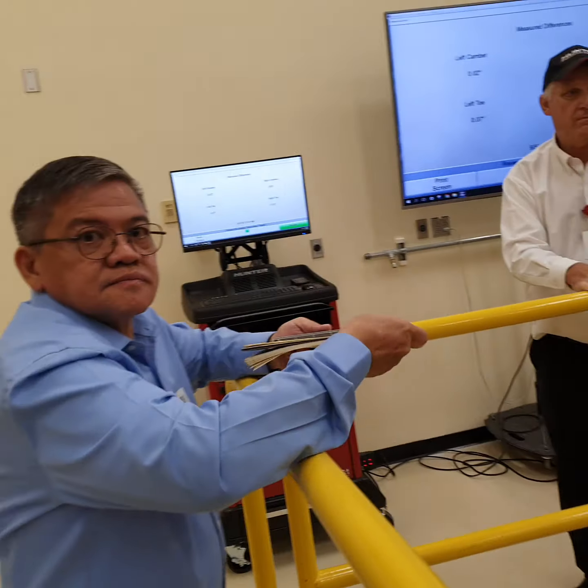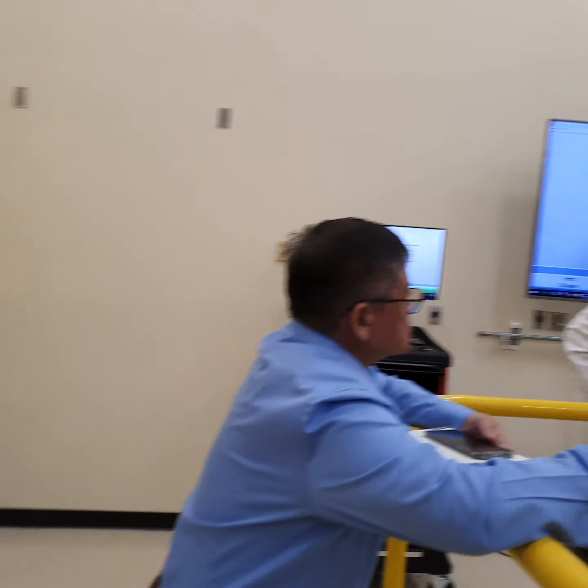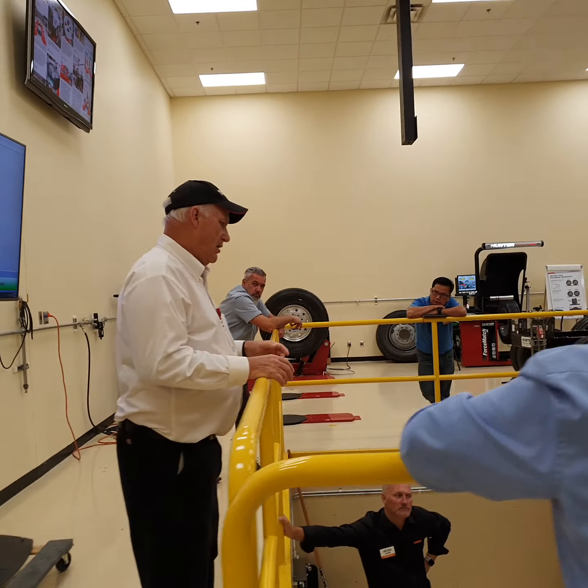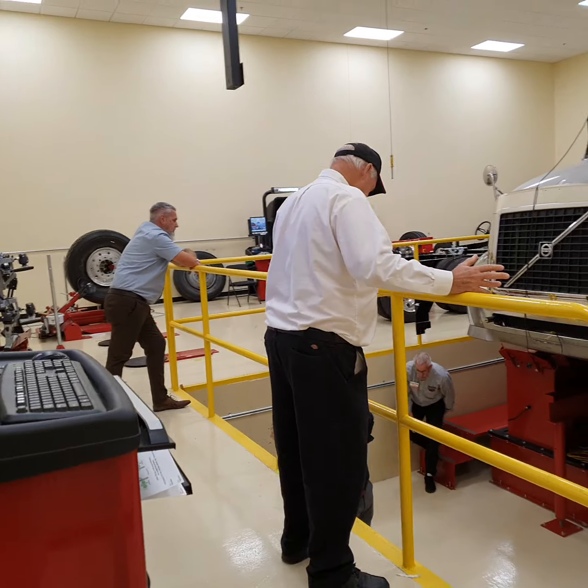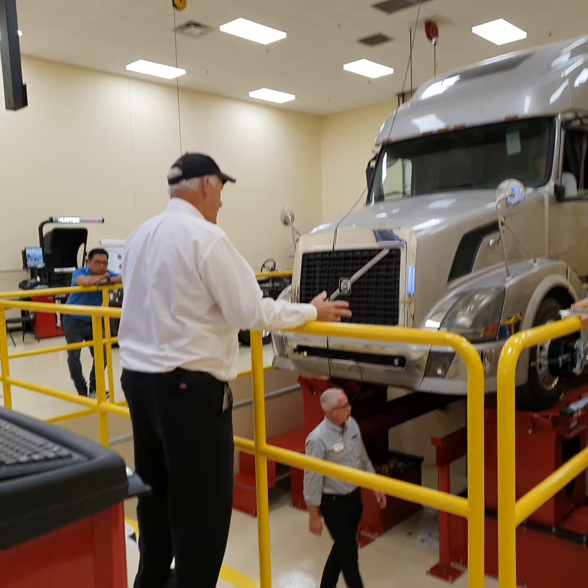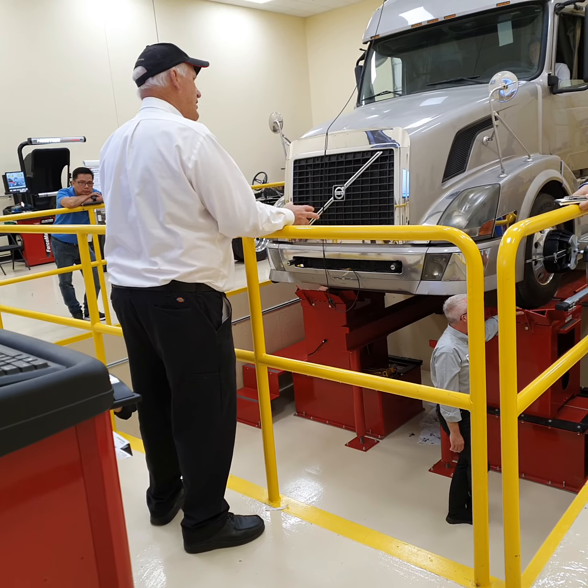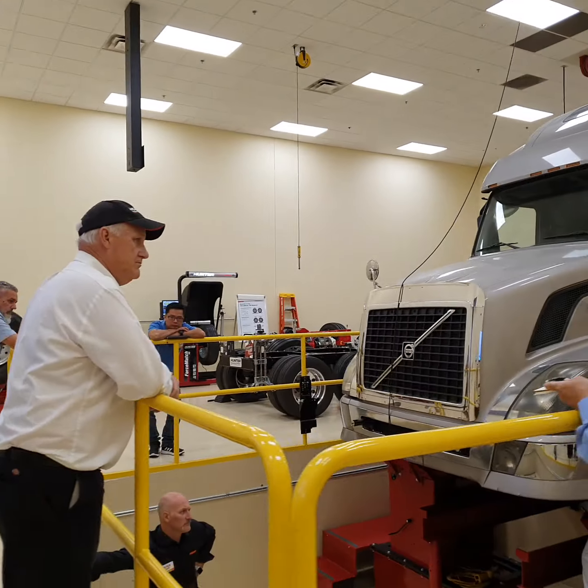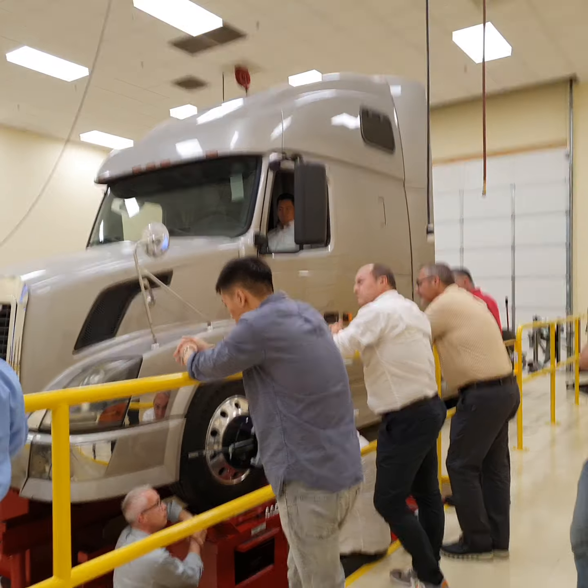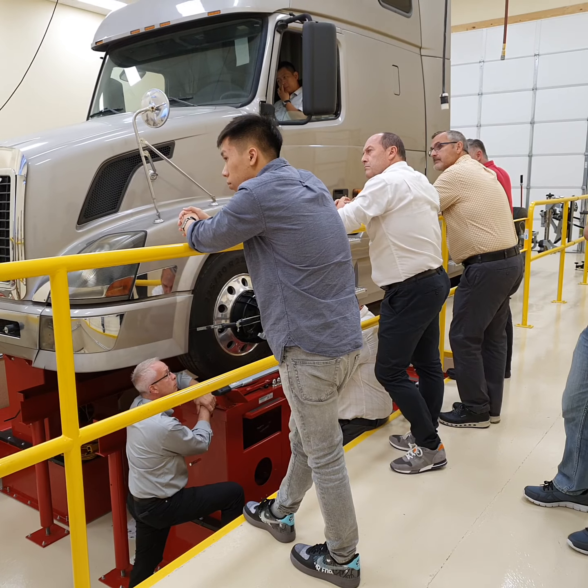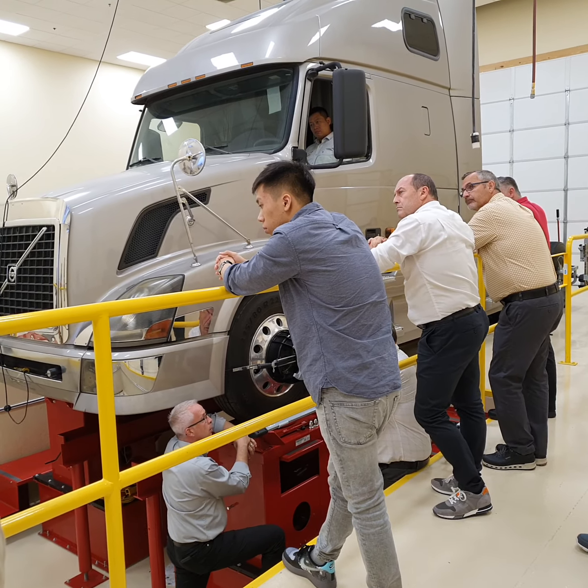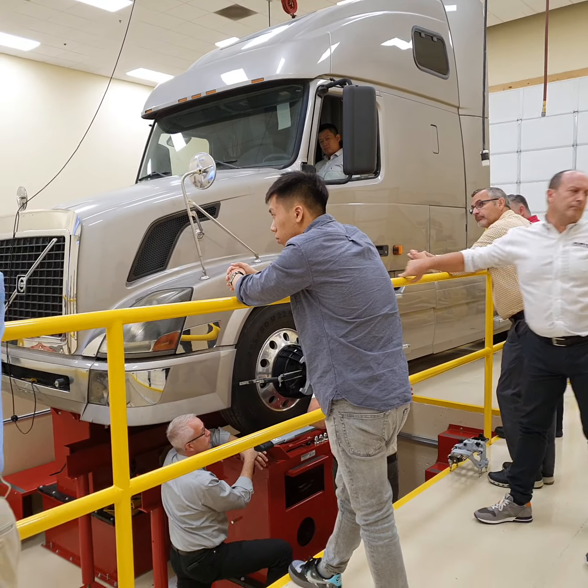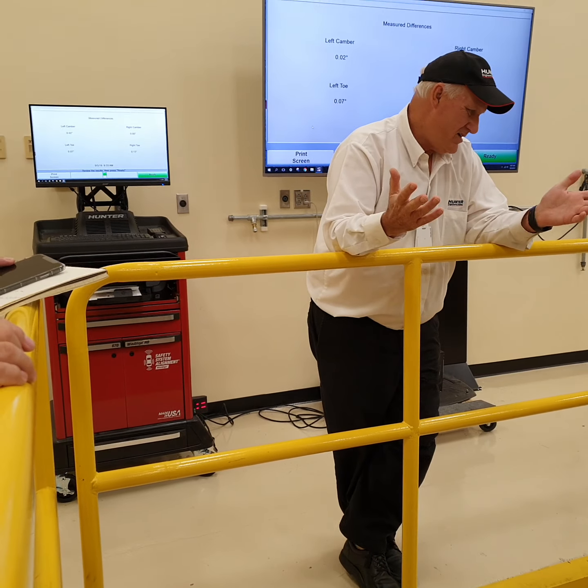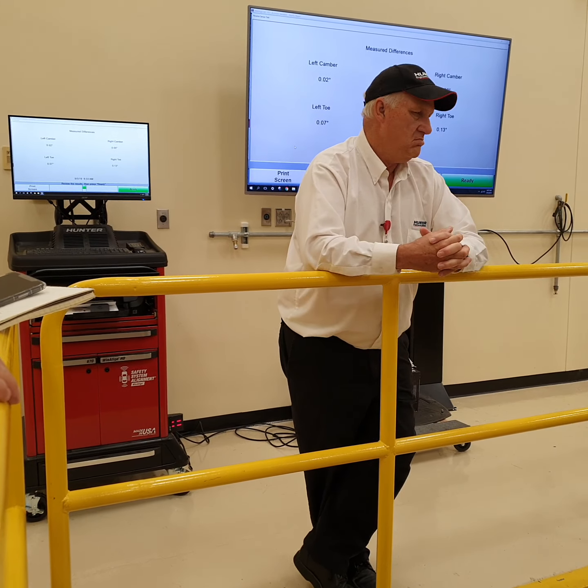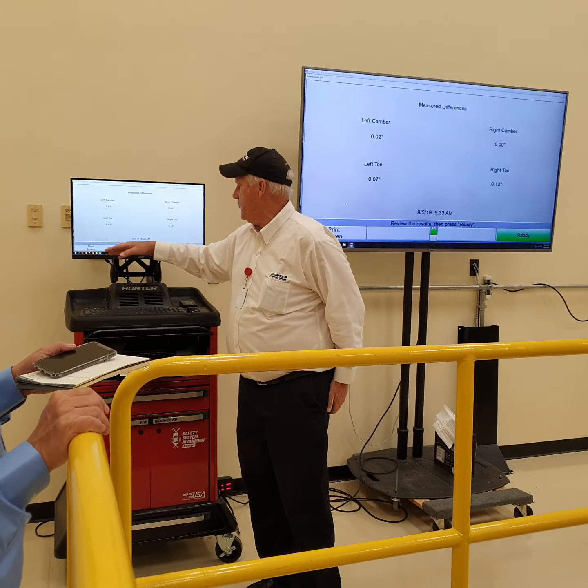So when the difference is too high, what can I do? Do I need new adapters? No, then what we would do is check calibration. So now I need to get the calibration bar, and I go through what they call a zero count, which is a pretty quick check for toe. It's a pretty fast process. We can sell a calibration bar to a customer. We typically don't here because our service reps are pretty close. They know what they're doing. It's a pretty simple test. It would just be part of my weekly maintenance situation, for my reference.